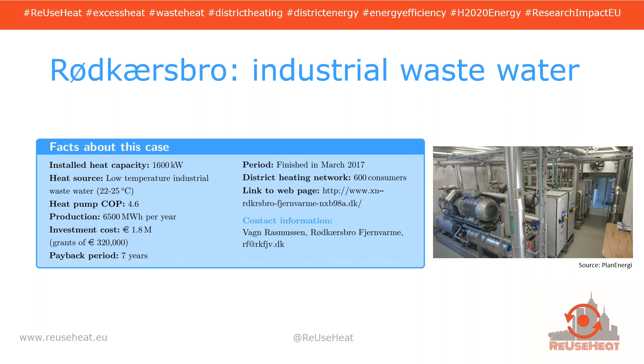But since the project was finished, they have experienced a little change in the performance of the heat pump. They're running with a slightly lower COP than expected, due to a change in temperatures at the dairy, which is no longer about 20 degrees but below that, around 17 degrees. This was due to the dairy optimizing their own industrial processes, which lowered the wastewater temperature. So they're not getting as much energy from the heat pump as expected, which also reduced its capacity by 300 kilowatts.